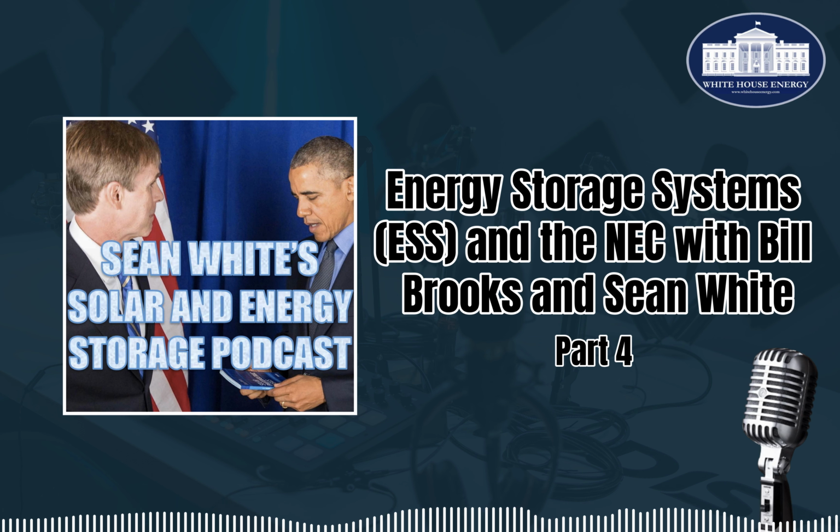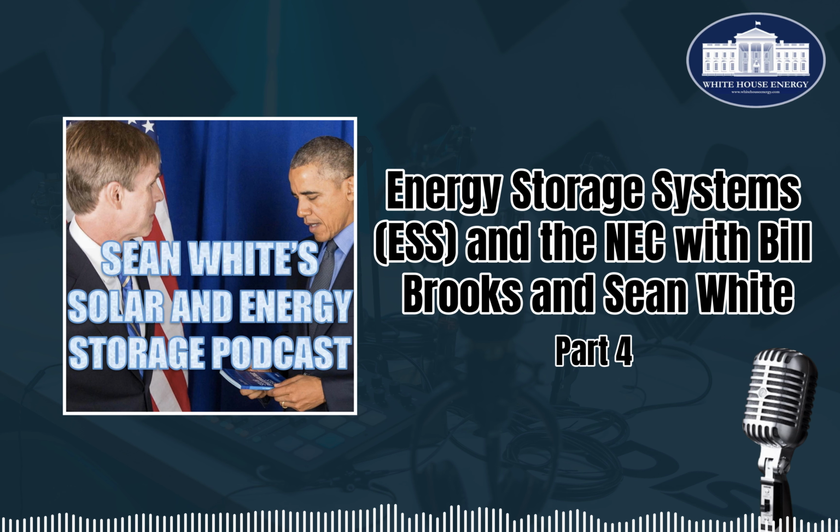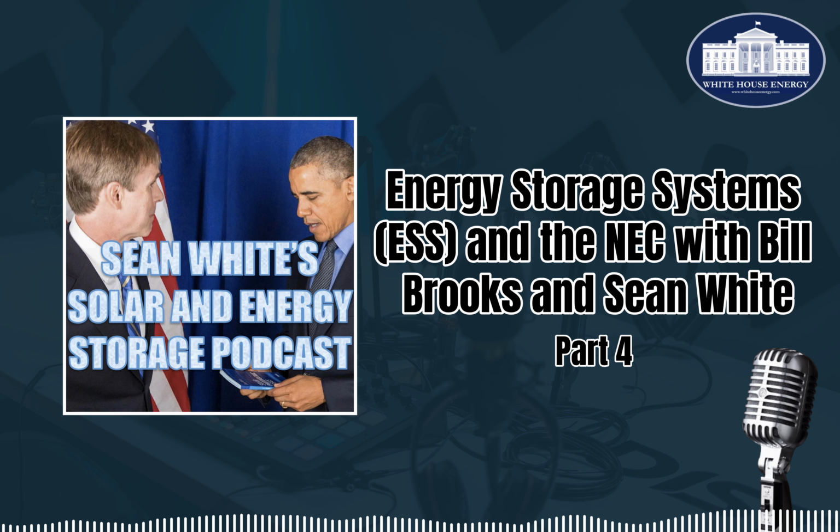So then when we're doing this with adding solar or energy storage, today's energy storage day, but it's the same thing for solar, instead of just taking that 150 amps, what we could do is we go 150 amps plus 125% of inverter current. So there's a 32 amp inverter, that's an energy storage inverter today, times 1.25 is 40 amps, that's 125% of inverter current. And so then we end up with 190. So there, 150 plus 40 is 190.